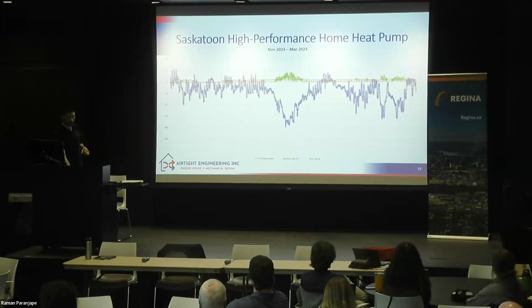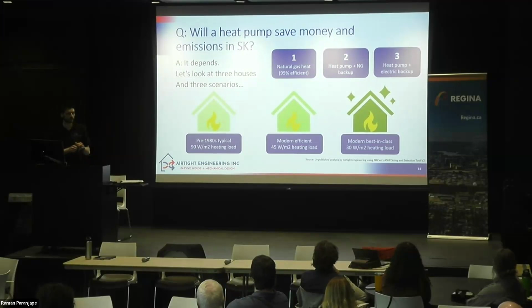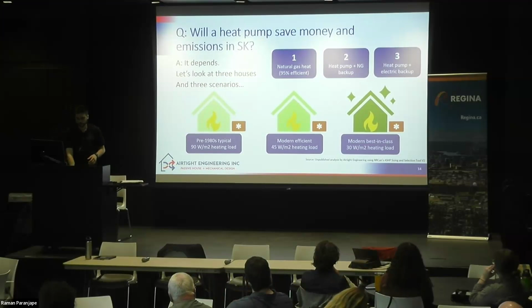Next question: will a heat pump save money and emissions in Saskatchewan? I did a little bit of analysis, looking at a few different scenarios. I looked at natural gas heat with a high efficiency furnace as my base case, then compared a heat pump with natural gas backup and a heat pump with electric resistance backup. I also looked at three types of house: one is a pre-1980s house with a higher heating load, one is a modern efficient house with a lower heating load, and then a modern best-in-class house, which is a very efficient house. There's my little heat pump symbol.